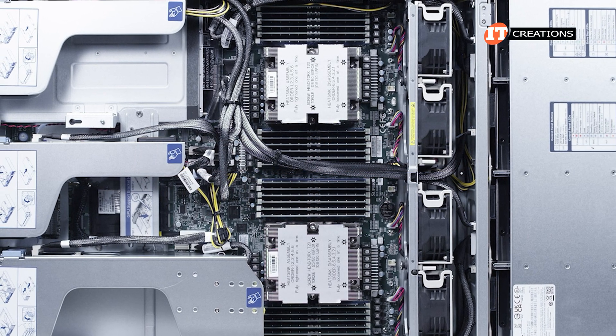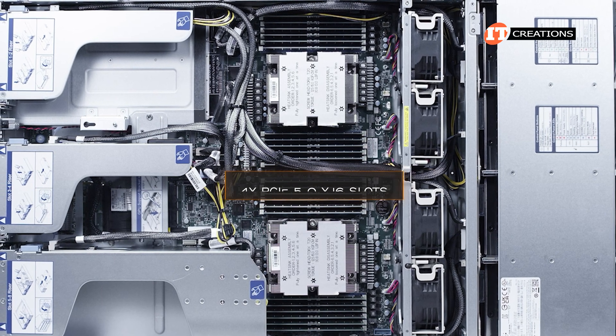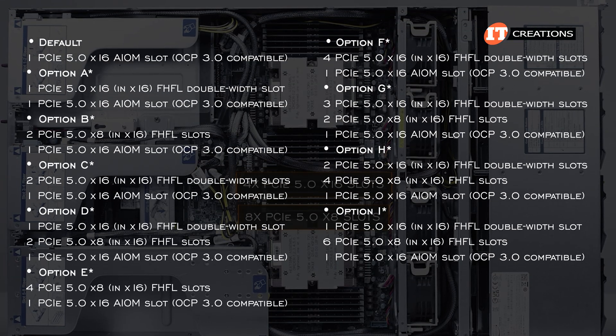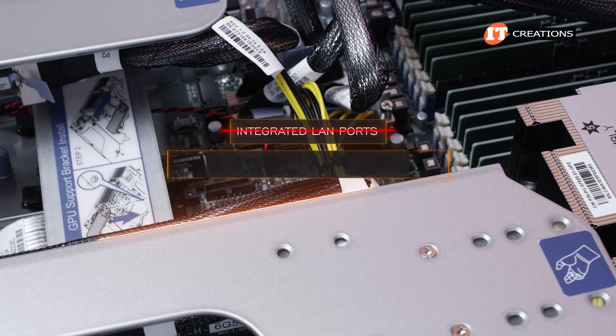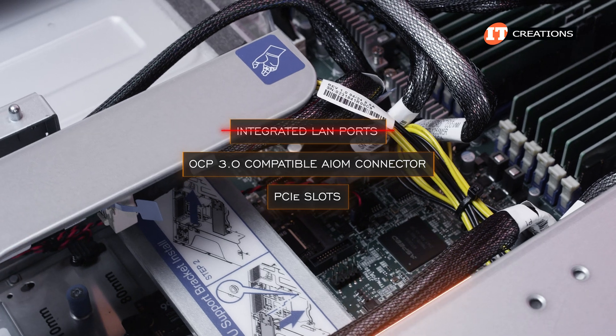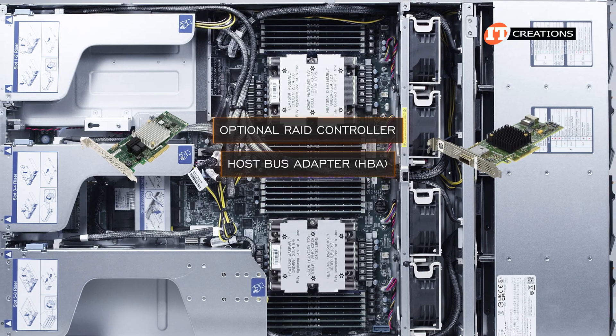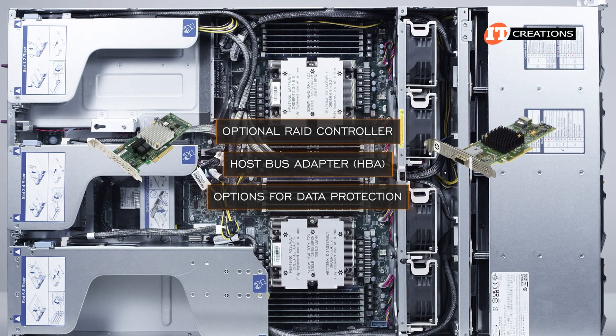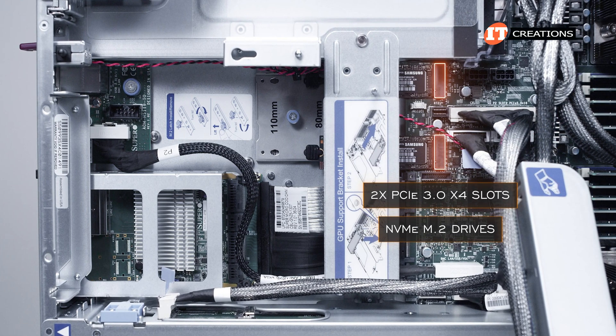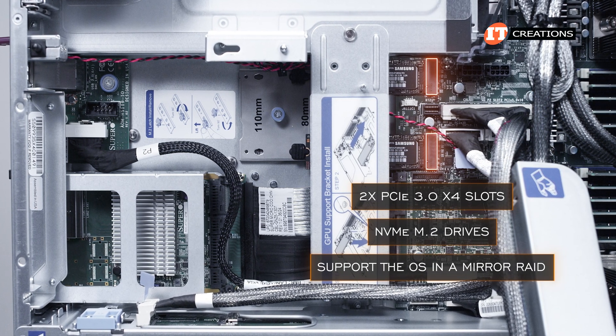A little more about those PCI slots: the basic configuration is either 4 x16 slots or 8 x8 slots, with combos in between. There are no integrated LAN ports — you will be using either the OCP 3.0 compatible AIOM connector or one of those PCI slots for network communications, or to support an optional RAID controller or host bus adapter for storage control. In addition, there are two PCI 3.0 x4 slots on the system board for NVMe M.2 drives, which can support your OS in a mirror RAID for redundancy and resiliency.